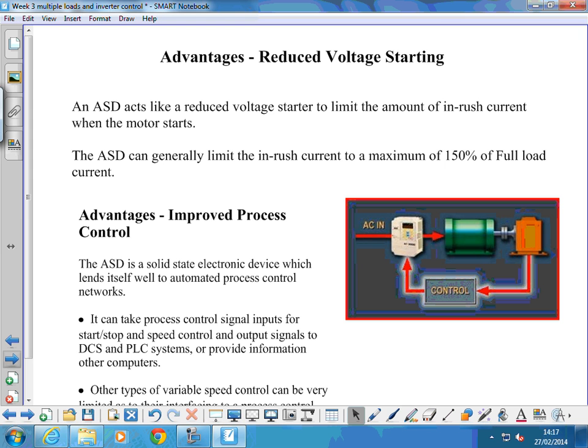Reduced voltage on starting. An ASD acts like a reduced voltage starter to limit the amount of inrush current when the motor starts. So you get a lot less inrush current on starting with a motor run from an inverter than you would from a direct online starter. The ASD can generally limit the inrush current to a maximum of 150% of the full load current. And that's quite a lot lower than you would expect to get from direct online starting.